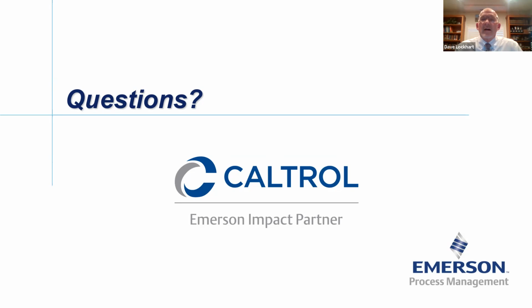Hey, Tom, this is Dave Lockhart. I wonder if you could talk a little bit about frequency of pulling samples, and if you have some guideline for what assets are better to be monitoring and not really worth monitoring, because there is a cost to all of this. So, absolutely, a little guidance on that. Anything that's running 24/7, has no redundancy, and is going to be extremely impactful if it fails, you want to monitor. If you're going to monitor it through a PdM program, a route-based program, you really should be doing those monthly. Most hospitals we do on a quarterly basis, and we've found that that seems to be fine, even if the units are running 24/7.